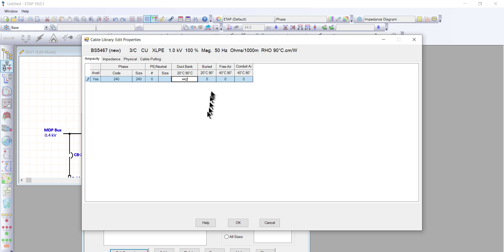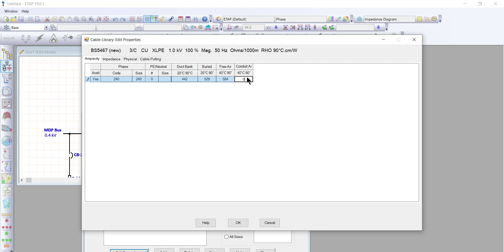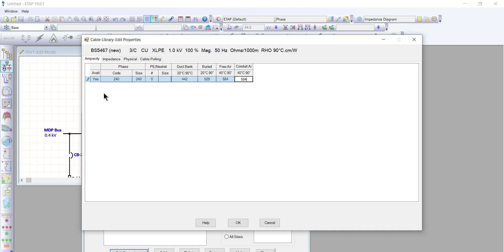For the duct bank, the ampere rating will be 442 amperes. For the buried rate, it will be 529 amperes. For free air, it will be 584 amperes — the same as the conduit. We have completed the ampacity section.